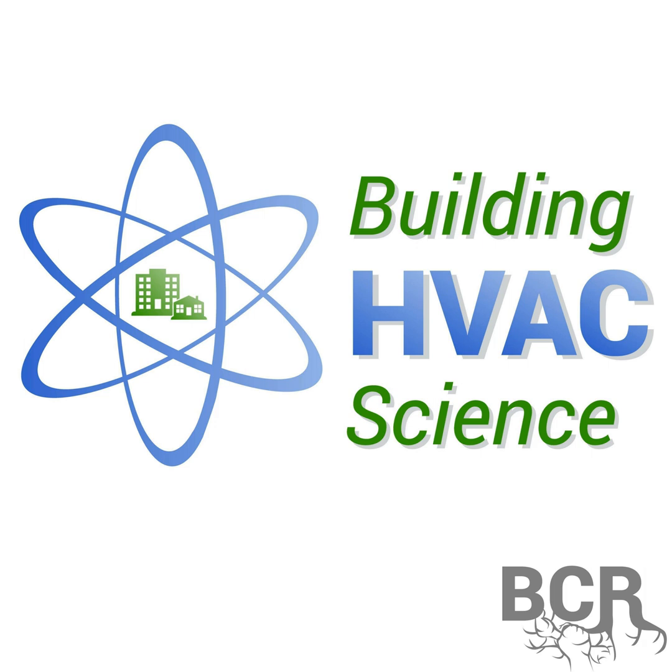And what's quite spectacular about that system, and that we're very proud of developing, is that it's a very modern, technologically advanced system. It's now over 10 years old, but it has to operate from minus 40 Fahrenheit to 140 Fahrenheit. So that's basically what the mil-spec 810 standard requires. In addition, it has to blow air that's at 6 to 7 psi, which doesn't sound like a lot of pressure, but in terms of blower power, a lot of the air conditioning is just getting the heat from the blower power out of the air, along with the extreme conditions it runs in.